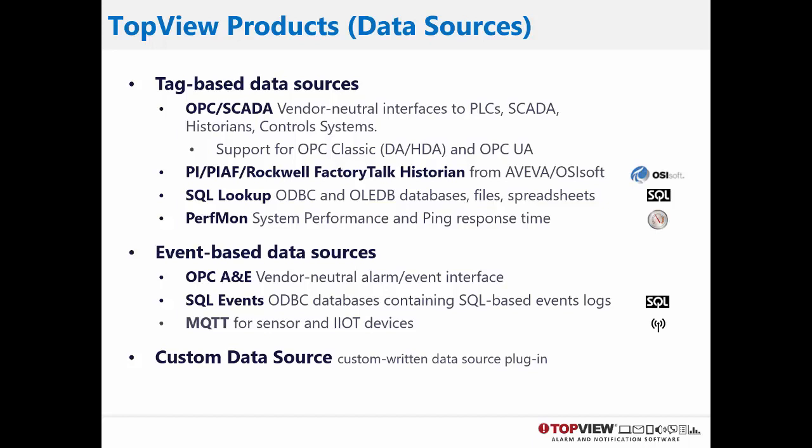Event-based data sources deliver new alarm events to TopView and require TopView to parse the events to determine the alarm and state changes. OPC Alarm and Events support systems that provide OPC A&E servers. TopView for SQL Events monitors alarm and event records written by systems to SQL databases. TopView for MQTT allows TopView to receive and parse incoming MQTT messages. MQTT is a lightweight protocol commonly used by remote sensors to send their data to subscribers.